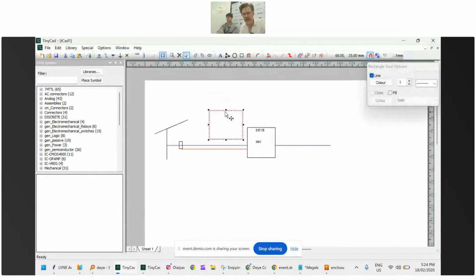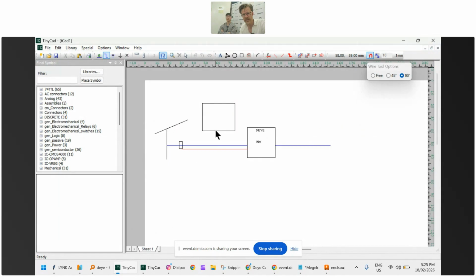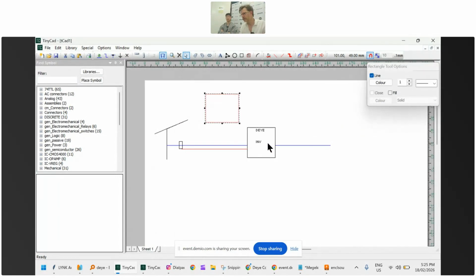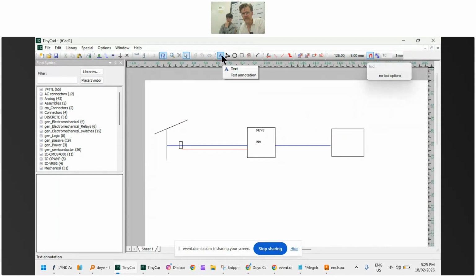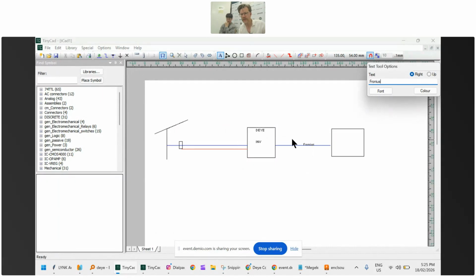Now, if I put it on the grid side, then it's just going to act like a normal grid tie inverter, governed by its own internal rules as to how it exports to the grid. But when the grid goes down, it's just going to go down. It's not going to support the system in a blackout because it's not on the backup circuit. So that's pretty straightforward. There's not really a lot you need to do with the inverter in that scenario, unless you've got some complicated export limitation because the total power of the two of them is more than what you're allowed to export. But the common scenario we get asked about is when the AC coupled inverter, let's call it Fronius, is on the load side.